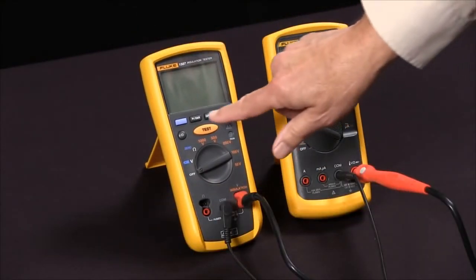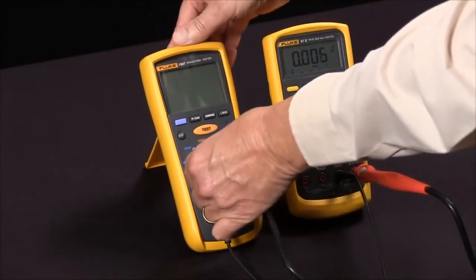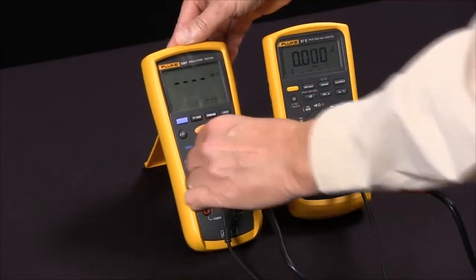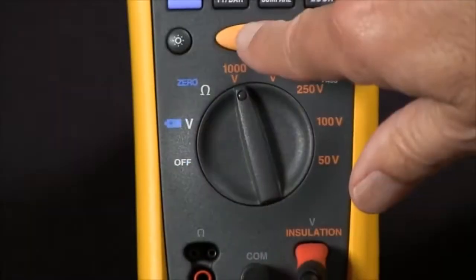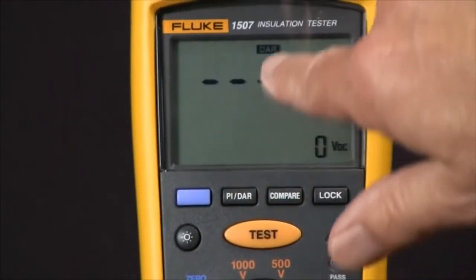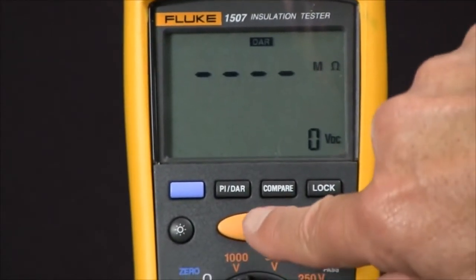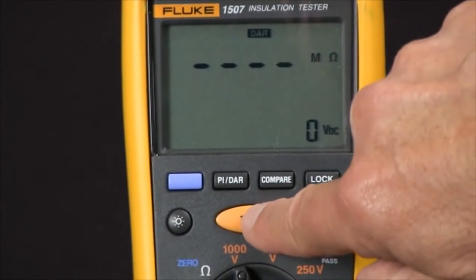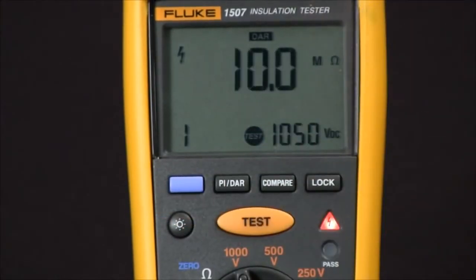We're going to pick 1,000 volts, so we rotate our selector knob to 1,000 volts. We select our test. In this case, I'm going to do DAR, dielectric absorption ratio, and I push the test button, and it begins the test.